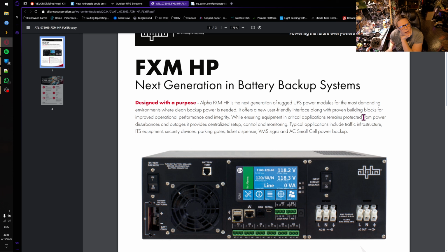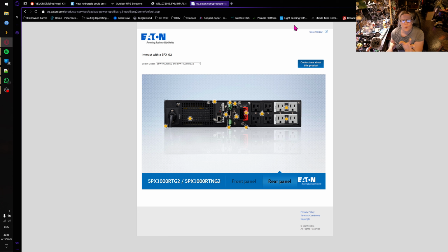What else should I be saying? I've got 20 minutes in here, and I think I've expressed my point well enough. To summarize, when you hook up a server, if you're not using DC power supplies in said server and you're hell-bent on using a UPS, one, use a reputable brand like Eaton or Alpha or Emerson or something higher end. You want to stay away from Tripp Lite.